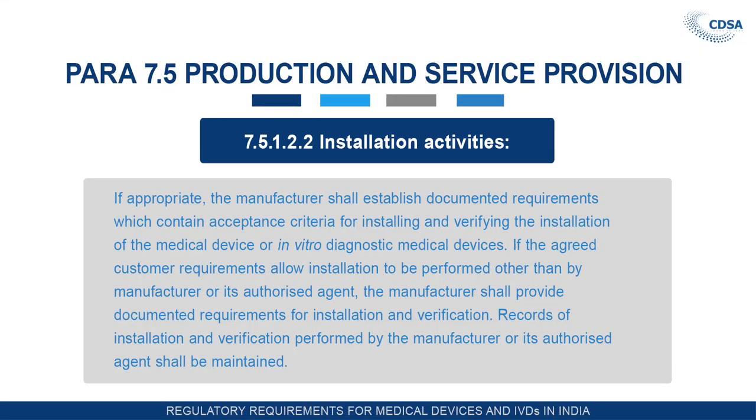If appropriate, the manufacturer shall establish documented requirements which contain acceptance criteria for installing and verifying the installation of a medical device or in vitro diagnostic medical device. If the agreed customer requirement allows installation to be performed other than by manufacturer or its authorised agent, the manufacturer shall provide documented requirements for installation and verification. Records of installation and verification performed by the manufacturer or its authorised agent shall be maintained.